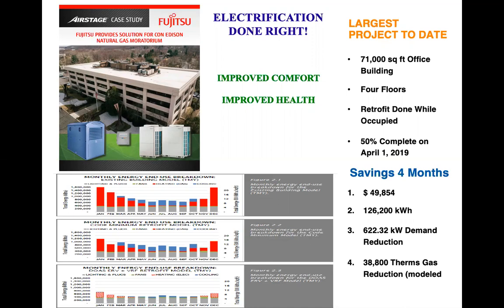With 50% completed by April 1st last year, so a year ago, they had accomplished, in just a matter of a few months, almost $50,000 in savings over just 4 months at this point, when this slide was done. What you'll see on those graphs are, the top graph is the building as we found it. So heating is red, cooling is blue, green, there's just a little green line as fans, and then the gray is plug loads and lights.